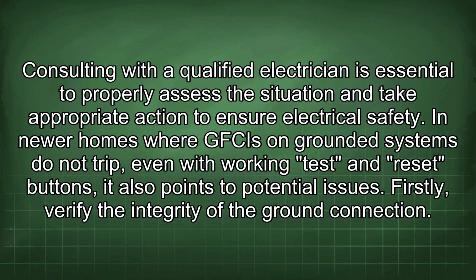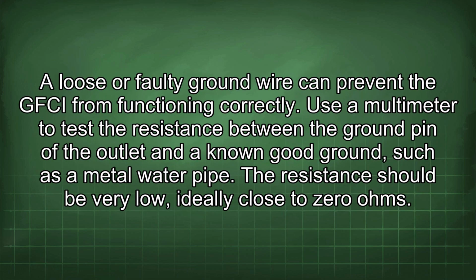Firstly, verify the integrity of the ground connection. A loose or faulty ground wire can prevent the GFCI from functioning correctly. Use a multimeter to test the resistance between the ground pin of the outlet and the known good ground, such as a metal water pipe.